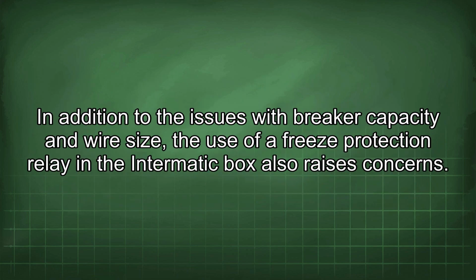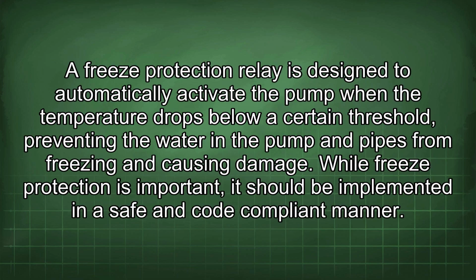In addition to the issues with breaker capacity and wire size, the use of a freeze protection relay in the Intermatic box also raises concerns. A freeze protection relay is designed to automatically activate the pump when the temperature drops below a certain threshold, preventing the water in the pump and pipes from freezing and causing damage. While freeze protection is important, it should be implemented in a safe and code-compliant manner.